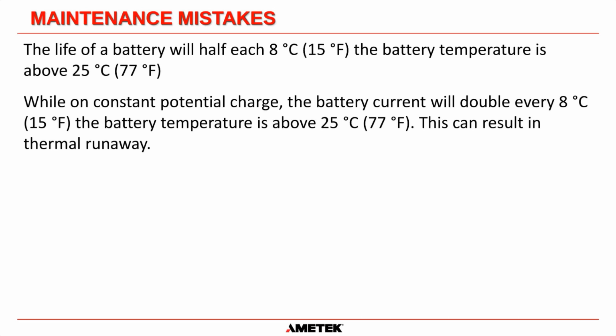And then also what you've got to understand is, while on constant potential charge, the battery current will double every 15 degrees Fahrenheit that you are above 77 degrees, okay? And for a valve regulated battery especially, that can result in thermal runaway. Because what happens in thermal runaway is, if the current increases, there's more current than necessary going into the battery now. So that causes the battery to heat up. As the battery heats up, it takes more current. That more current causes the battery to heat up even further. And then it's a snowball effect that is called thermal runaway.